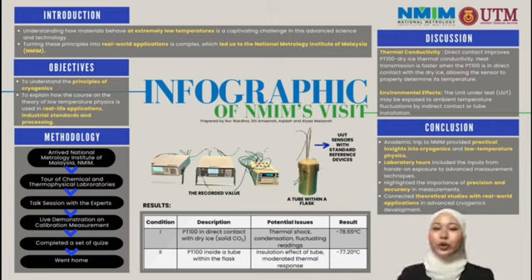In our study, we observed that the PT100 sensor in direct contact with dry ice provided temperature readings closer to the standard reference compared to the PT100 placed inside a tube or with indirect contact. This difference is due to the higher thermal conductivity achieved through the direct contact. Direct contact allows for more efficient heat transfer, enabling the PT100 to obtain a more precise reading of the dry ice temperature. On the other hand, placing the PT100 inside a tube or indirectly can lead to variation due to environmental temperature fluctuation, affecting the accuracy of the measurement.